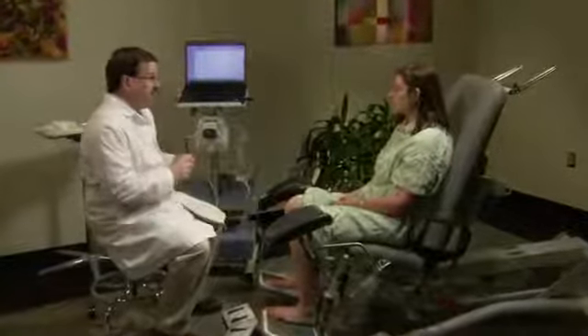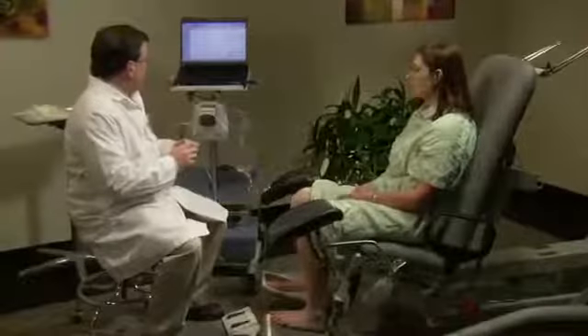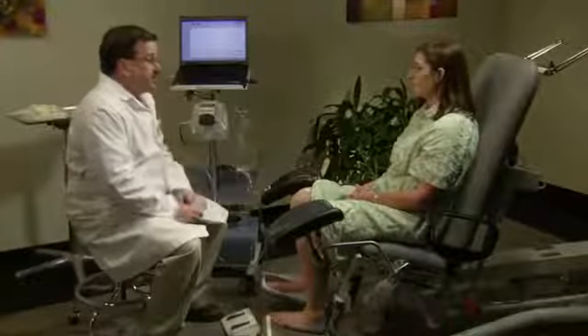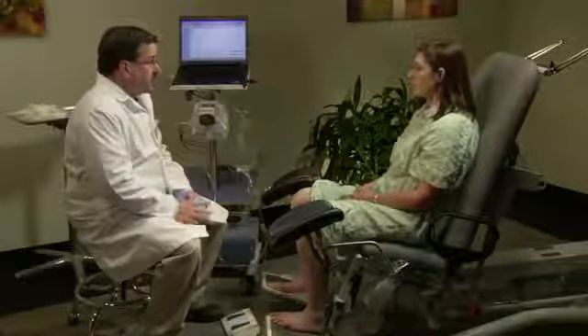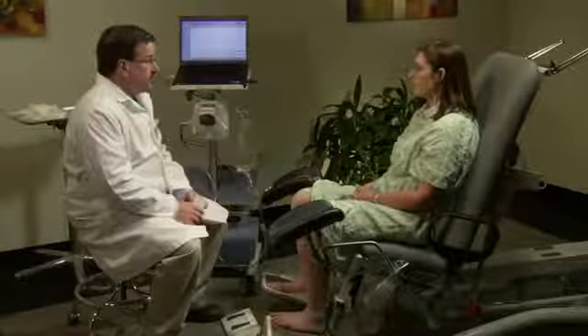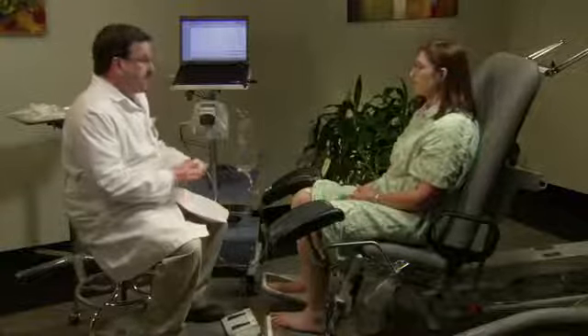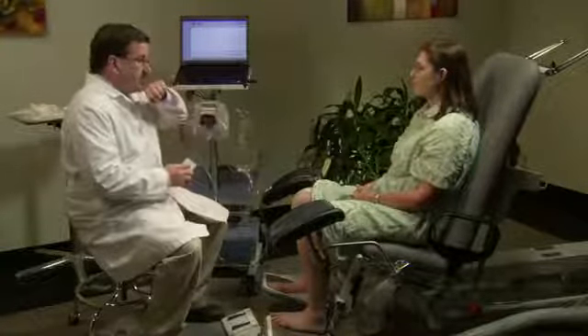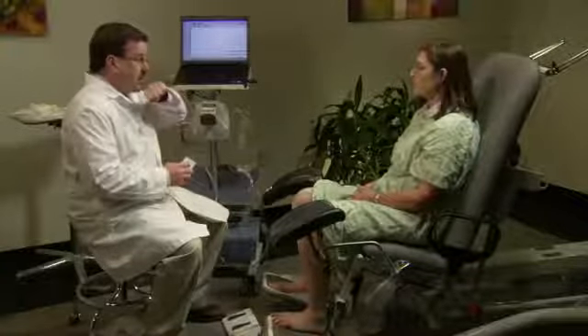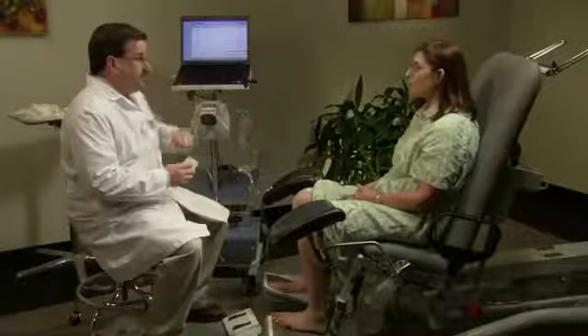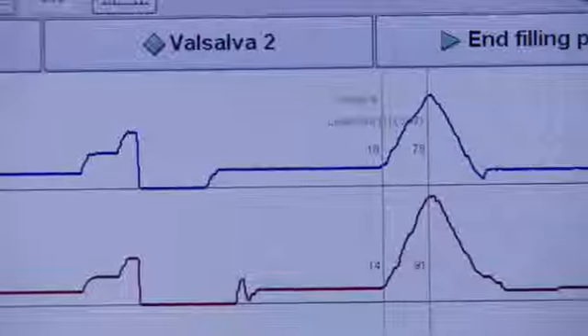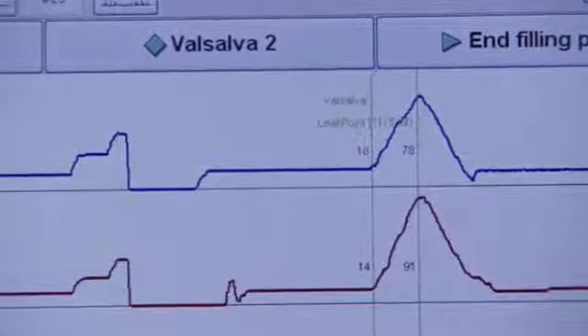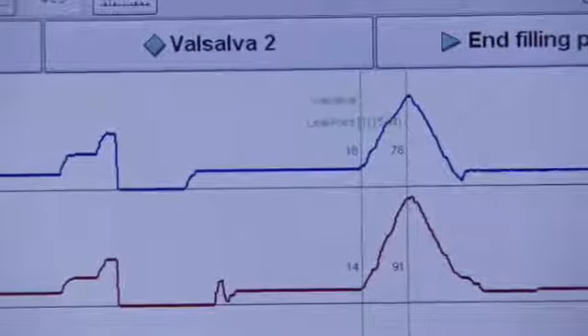The tech will also evaluate the patient for stress incontinence by performing Valsalva maneuvers and coughs at set intervals throughout the filling phase. To perform a Valsalva, press the Valsalva button and have the patient slowly bear down, tightening her abdominal muscles. If a leak occurs, the nurse will use the leak point button to label the leak. The printed results will show in detail the baseline pressure, the pressure where the leak occurred, and the difference in pressure.